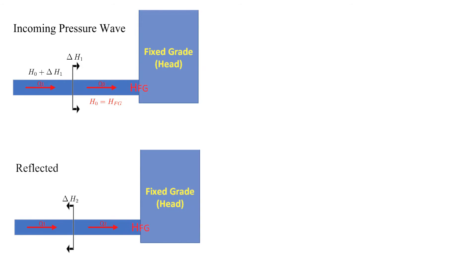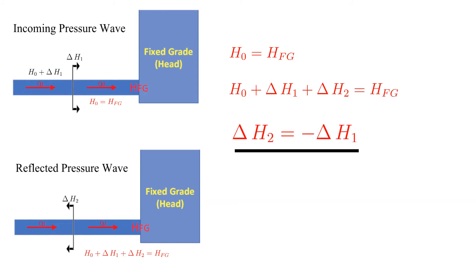Now let's put it all together. Since the head adjacent to the tank remains constant, the reflective wave, delta H2, must be equal in magnitude but of opposite sign as the incoming wave, delta H1. In other words, waves reflect negatively off of a large tank or fixed grade.